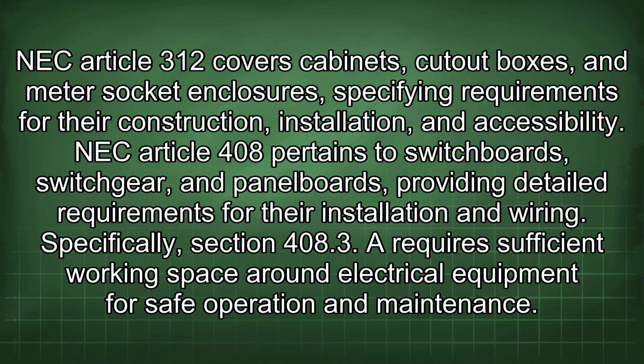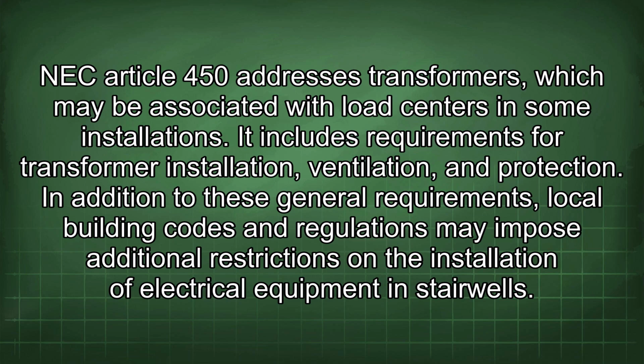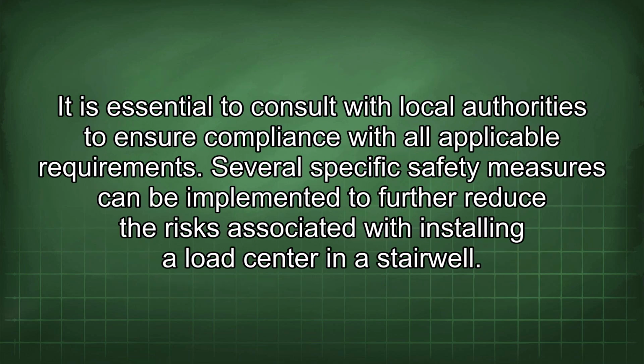NEC Article 408 pertains to switchboards, switchgear, and panelboards, providing detailed requirements for their installation and wiring. Specifically, Section 408.3 requires sufficient working space around electrical equipment for safe operation and maintenance. NEC Article 450 addresses transformers, which may be associated with load centers in some installations. It includes requirements for transformer installation, ventilation, and protection. In addition to these general requirements, local building codes and regulations may impose additional restrictions on the installation of electrical equipment in stairwells. It is essential to consult with local authorities to ensure compliance with all applicable requirements.